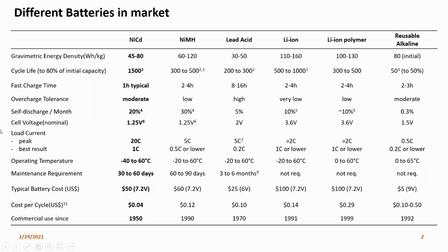A few factors I can say: we can charge the battery at higher speed, not like lithium ion, but nickel cadmium has a much bigger advantage than the lead acid battery. A very good difference is that it can operate at multiple temperature ranges, even at lower temperatures. We can see -40 to 60 degrees, where lead acid starts from 20 to 60 degrees. So that is a prime one we have.